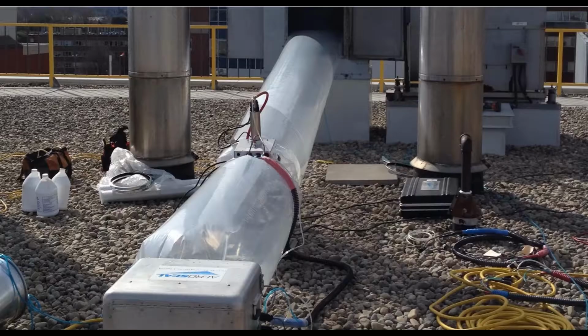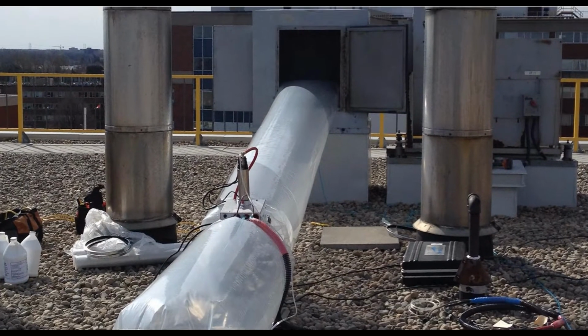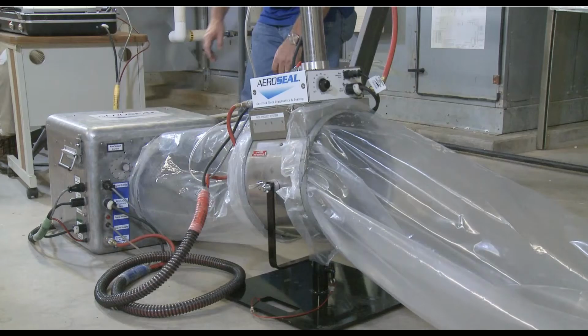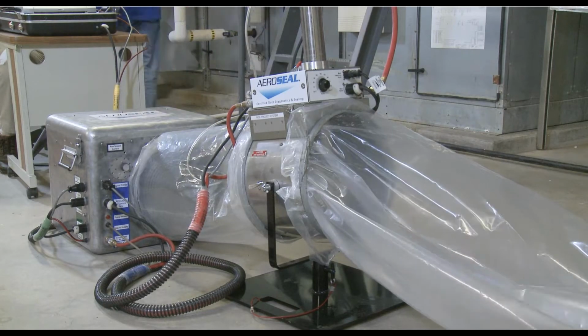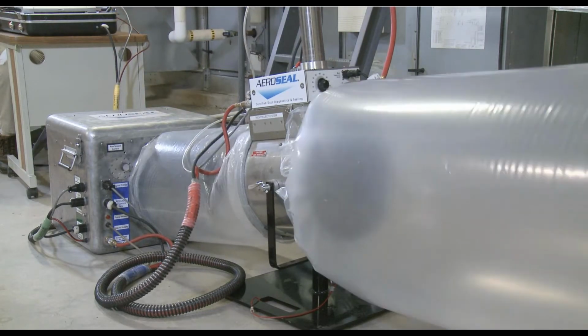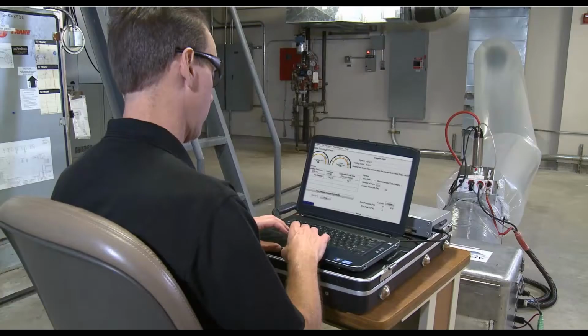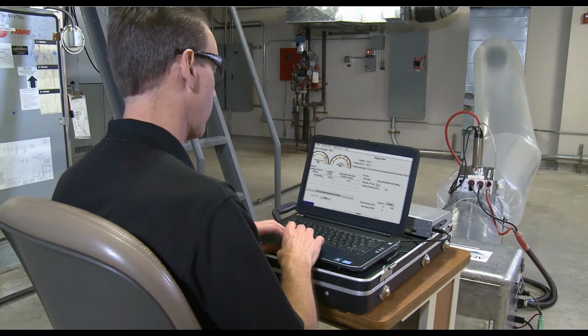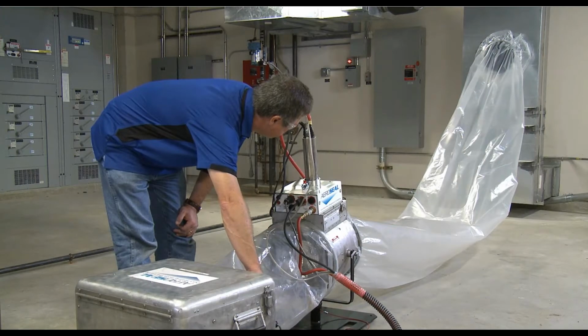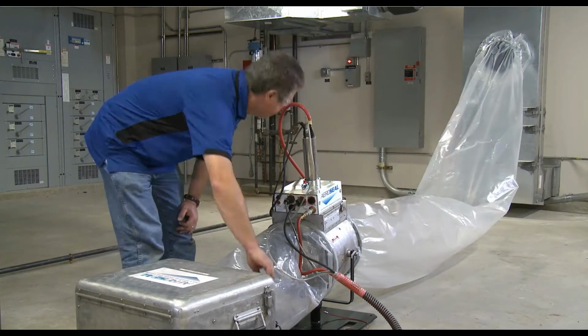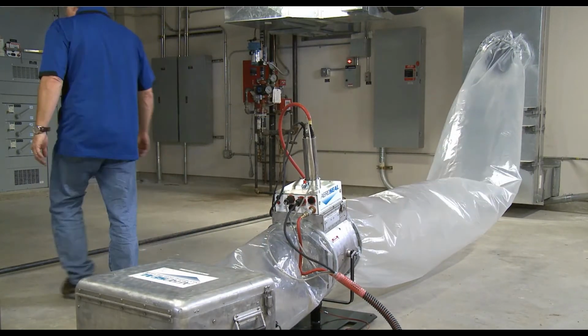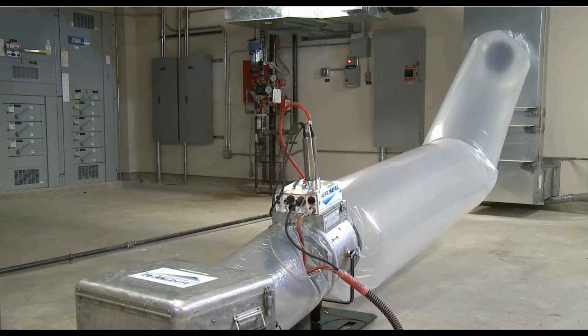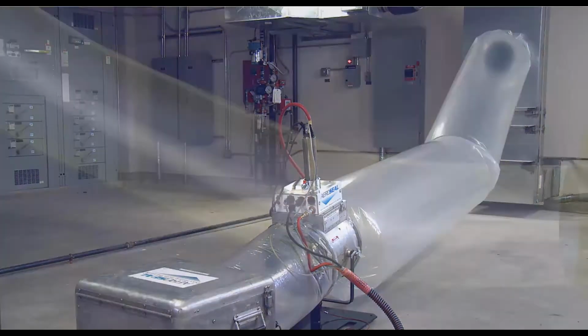A thing to note is you can see the different applications. Sometimes we're sealing on a rooftop, sometimes we're in a mechanical room like this. It depends on ease of access and the best way for us to get to the main trunk line of the ductwork. Sometimes it's a rooftop unit, so we have to do it through the drops of the rooftop. Sometimes it's an air handling unit in a mechanical room, where we can easily access the trunk and do our injection right there.